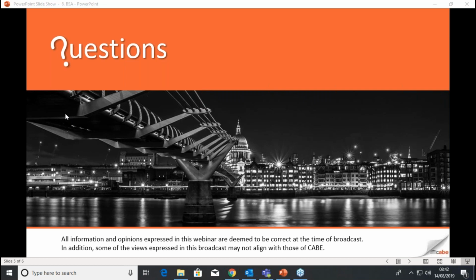So if anyone is looking to use a water mist system, they need to check carefully: has it been tested for the specific application, proven to work in it, do you understand the technology being specified, will it be maintainable and available long-term, and does the installer have the right credentials? I've jumped around a bit there, but hopefully that gives you a flavour that yes, we support water mist, but recommend doing so carefully at this stage.